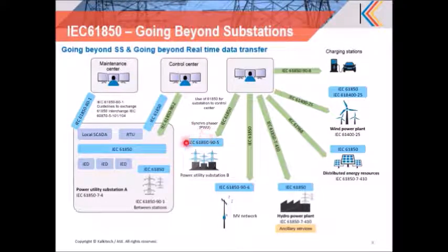substation communication with the WAMS requirement, the data transfer from the synchrophasors or PMUs to the control center for WAMS requirement. That has come as 90-5, in which R-GOOSE, routable GOOSE and routable sampled value exchange concepts came as part of 90-5.